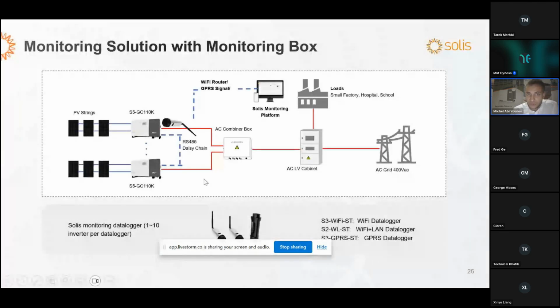First, the monitoring system. Our on-grid inverter, each stick can monitor up to 10 inverter. So if you have like up to 10 inverter, we can use only one monitoring stick, one Wi-Fi stick. No need to use other than one Wi-Fi stick. All we have to do is to connect the inverter through RS485 daisy chain. Okay, if you have more than 10 inverter, we can use two Wi-Fi stick.